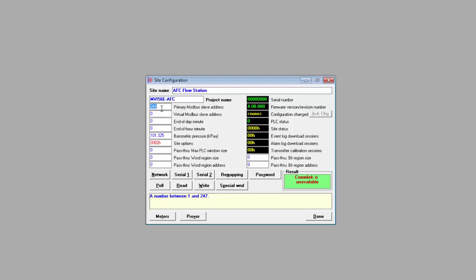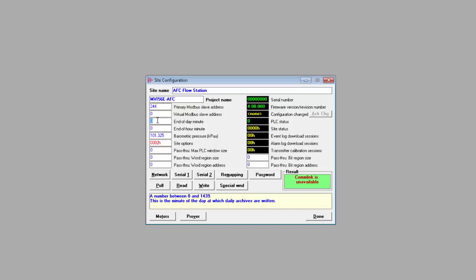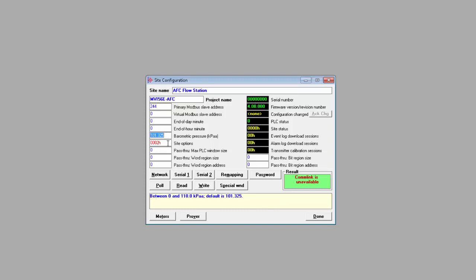The default should be fine, but you can change it to any address from 1 through 247. The Virtual Slave is used for more efficient data polling and setting its address to any value greater than zero will enable it. End of day and end of hour minutes specify when archives will be created. By default, zero minutes means midnight and you can go from zero to 1439. Zero for hour creates hourly archives at the top of each hour.